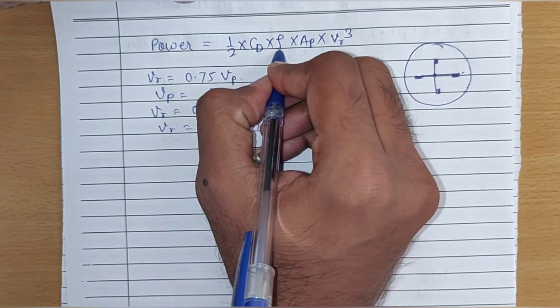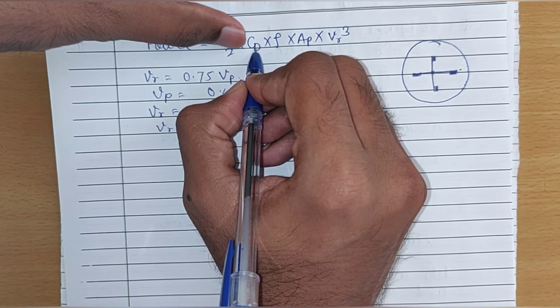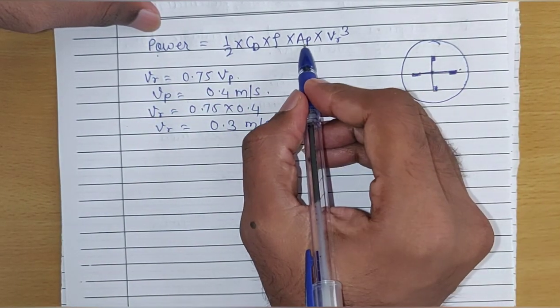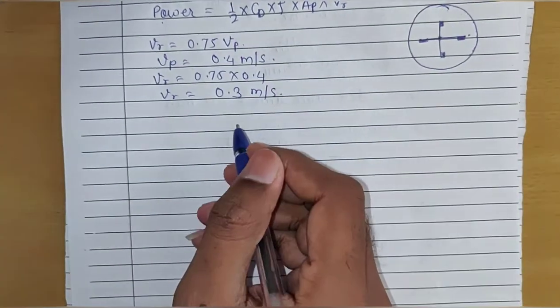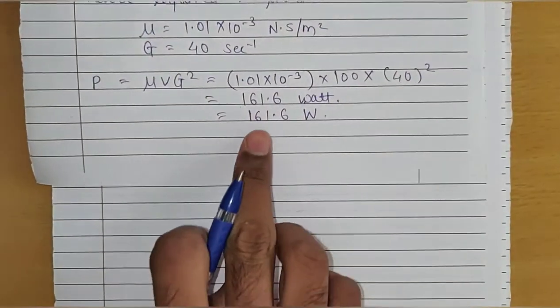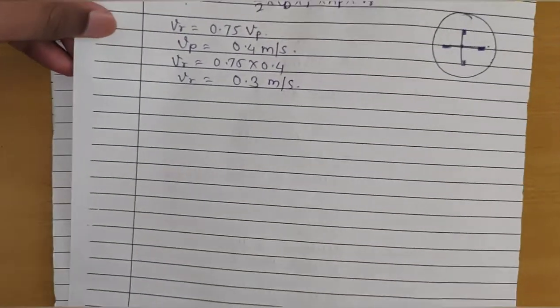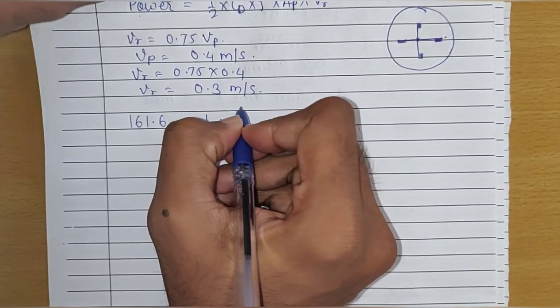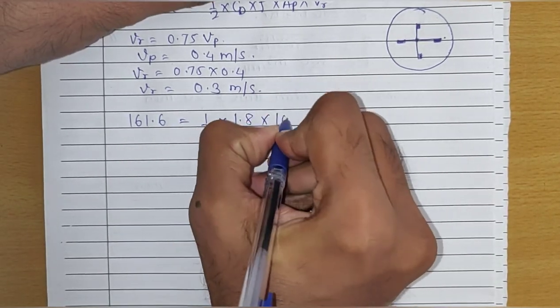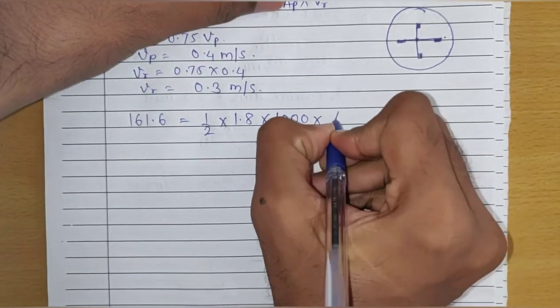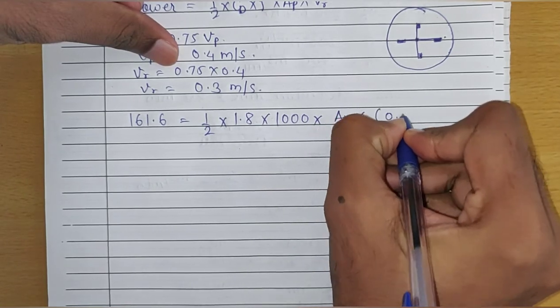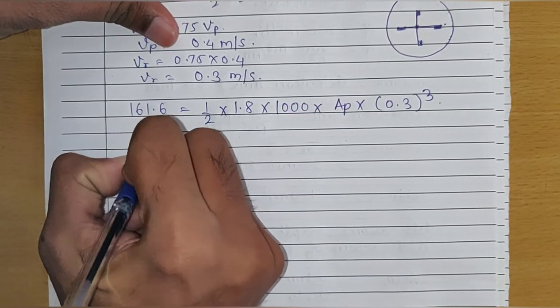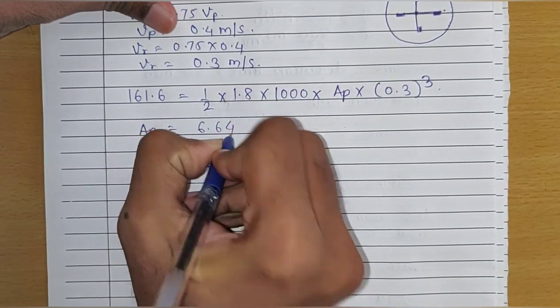We know the density of water is 1000 and the drag coefficient CD is between 0.8 to 1.9. We take CD as 1.8. Setting up the equation: 161.6 equals half times 1.8 times 1000 times area of paddle times 0.3 cubed. The only unknown is the area of paddle, and solving gives the area of paddle as 6.64 meter square.